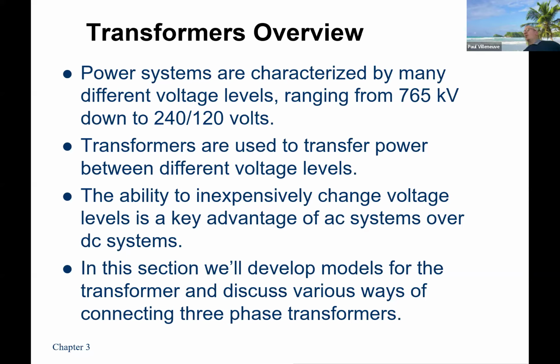Most of the transformers you will come across are oil filled. They're permanently sealed transformers. Like the pad mounts located across campus, there's no maintenance. They're designed to have no maintenance. But bigger transformers that carry a lot of power and a lot of changes have to be tested and maintained. Sometimes you have to change out the oil. So you run tests on those every year to every five years. And if those tests are run fairly regularly, usually a transformer will last you 20 to 40 years.